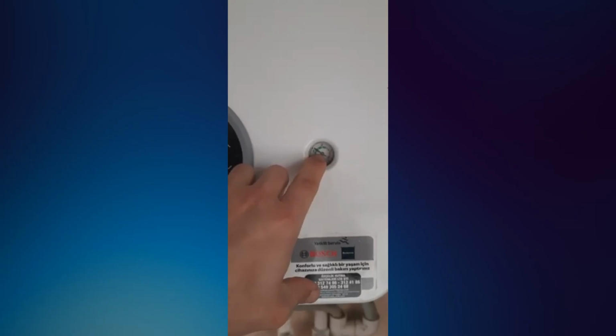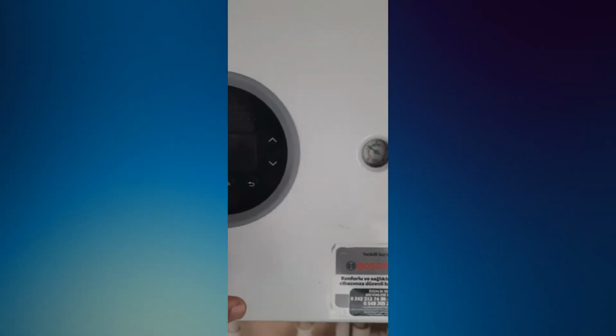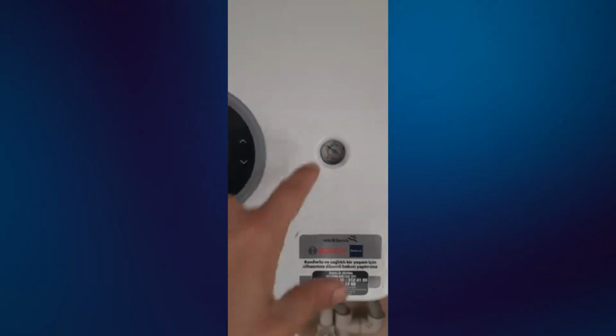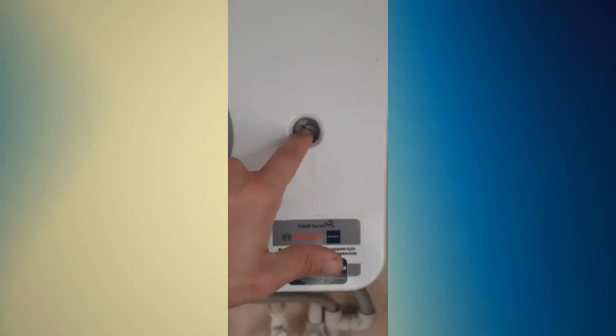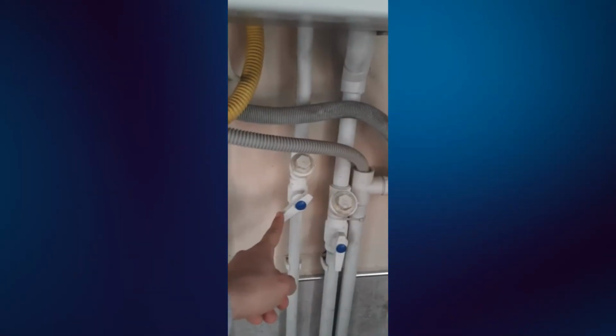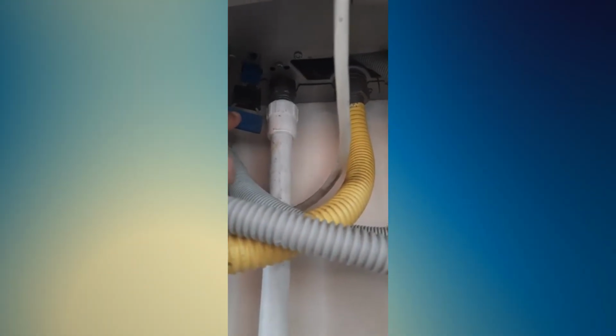If the pressure is below the normal range, you may need to top up the system using the filling loop or the built-in filling valve. On some boilers, this is a small filling tap under the boiler. On others, it may be a keyless filling link, a filling key, or a flexible silver hose. Turn the boiler off, let the system cool, and open the filling valve slowly. Watch the gauge carefully. When the pressure reaches the correct range, usually around 1 to 1.5 bar when cold, close the valve fully. Do not overfill the system. Do not leave the filling valve open. If the pressure rises too high, that can create another problem.